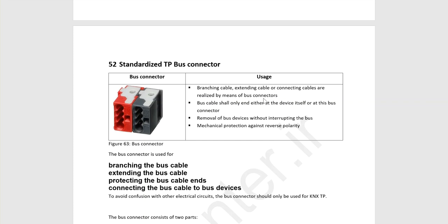So it is used to connect the devices to the bus. Also, if you want to extend your KNX cable, you should use this one. And you can branch it, okay? Because it has 4 input-output. The bus cable shall only end either at the bus device itself or at the bus connector. So if you are at the end of the bus cable, you should always use the connector.